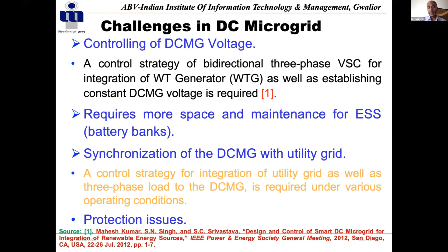The synchronization of DCMG with the utility grid is required, so synchronization panels and control philosophy must be utilized. Another issue is protection, because DC protection is more difficult than AC protection. But in DC protection, the converter itself is used as the protection system, controlling in such a way that if there is any fault, they can assess and control it, just like in high voltage DC transmission systems.